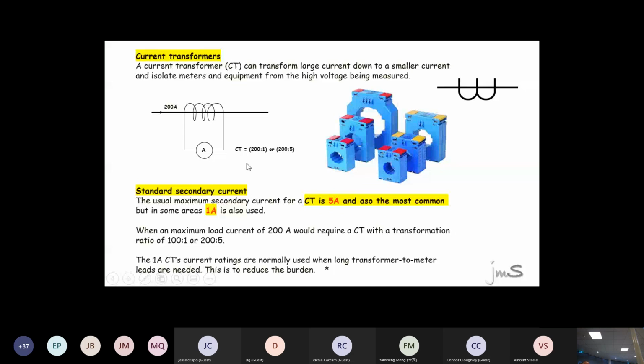So a CT is either rated 1 amp or 5 amp. But here comes another thing. I want to make this so clear that everybody hears it well. The normal secondary current of a CT is 5 amps, that is the normal one. But you also get it in 1 amp. So the standard one you normally buy is 5 amp, but you can get 1 amp ones as well. If they tell you there's a 1 amp one or a 5 amp one and you have to choose one, which one will you choose? In the exam, you're only allowed to choose one answer. What is the normal secondary current? 5 amps. Is that clear to everybody? Don't stuff that one up, please.